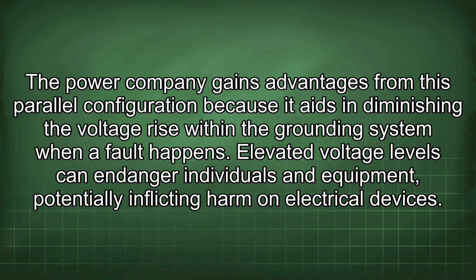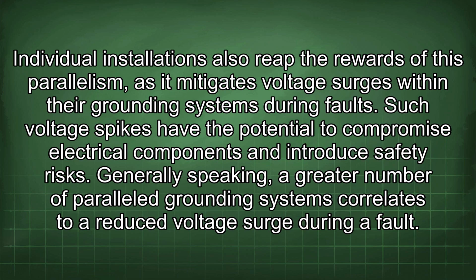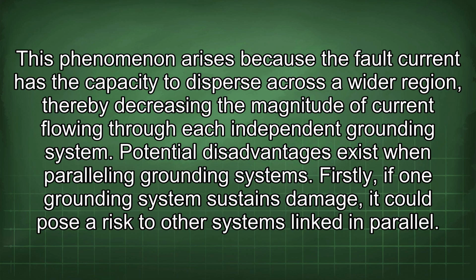Elevated voltage levels can endanger individuals and equipment, potentially inflicting harm on electrical devices. Individual installations also reap the rewards of this parallelism, as it mitigates voltage surges within their grounding systems during faults. Such voltage spikes have the potential to compromise electrical components and introduce safety risks. Generally speaking, a greater number of paralleled grounding systems correlates to a reduced voltage surge during a fault. This phenomenon arises because the fault current has the capacity to disperse across a wider region, thereby decreasing the magnitude of current flowing through each independent grounding system.